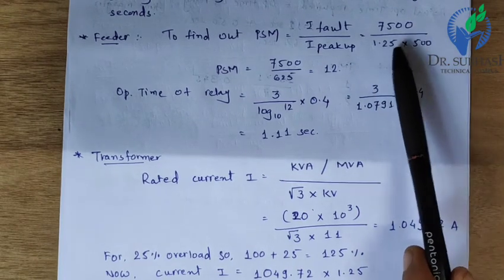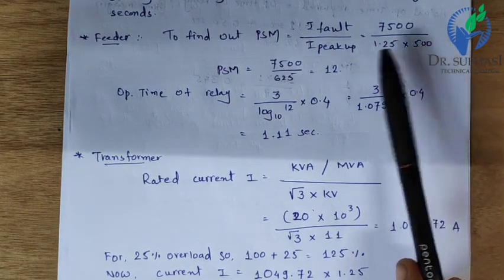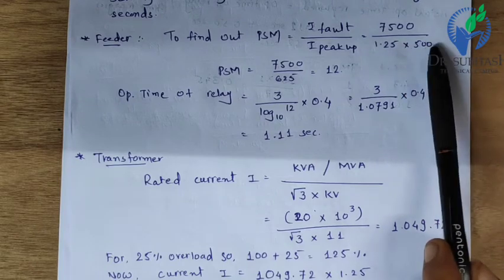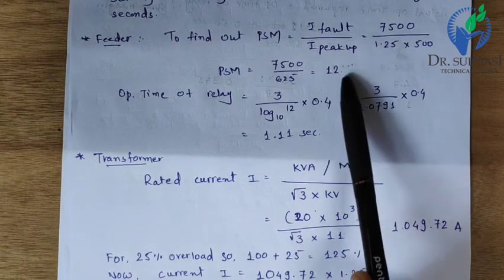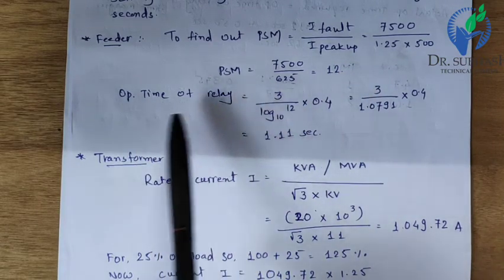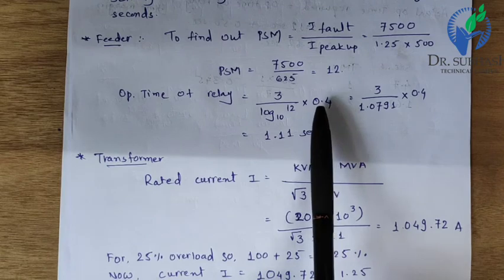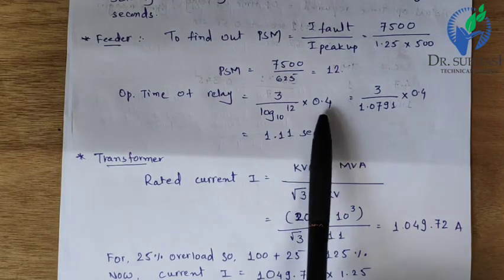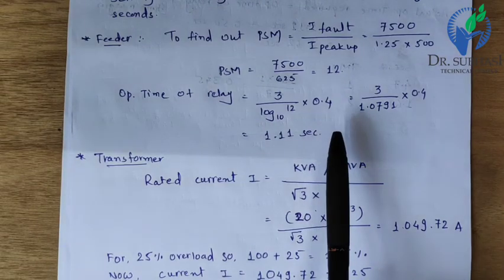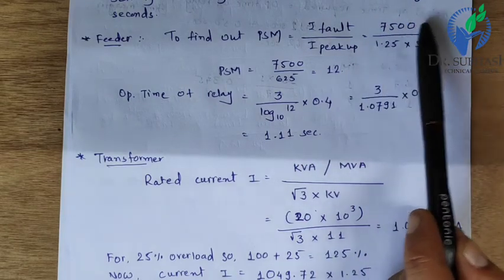Pickup current = 1.25 × 500 = 625 A. PSM = 7500 / 625 = 12. So the plug setting multiplier of the feeder relay is 12. Using the operating time equation T = 3 / (log10(PSM)) × TMS, with PSM = 12 and TMS = 0.4, the feeder relay operating time is 1.11 seconds.